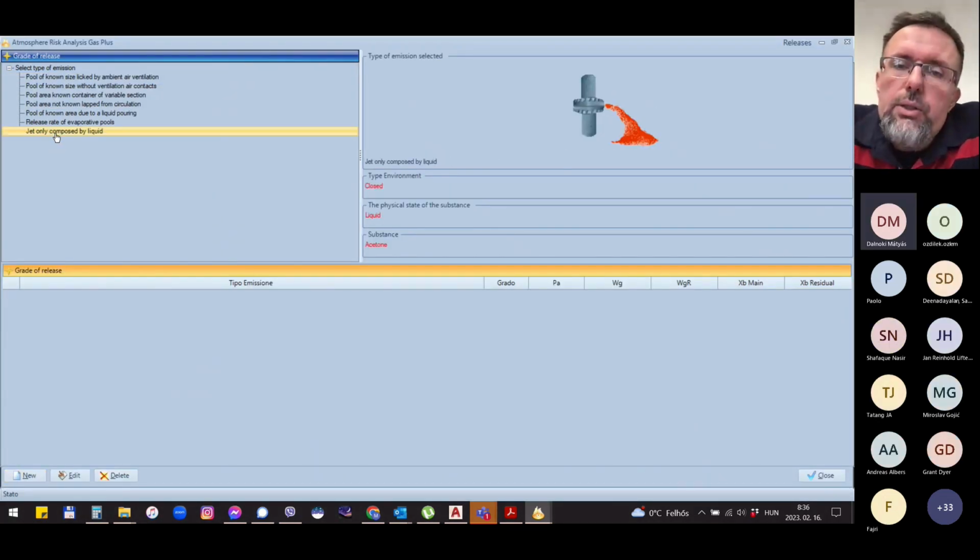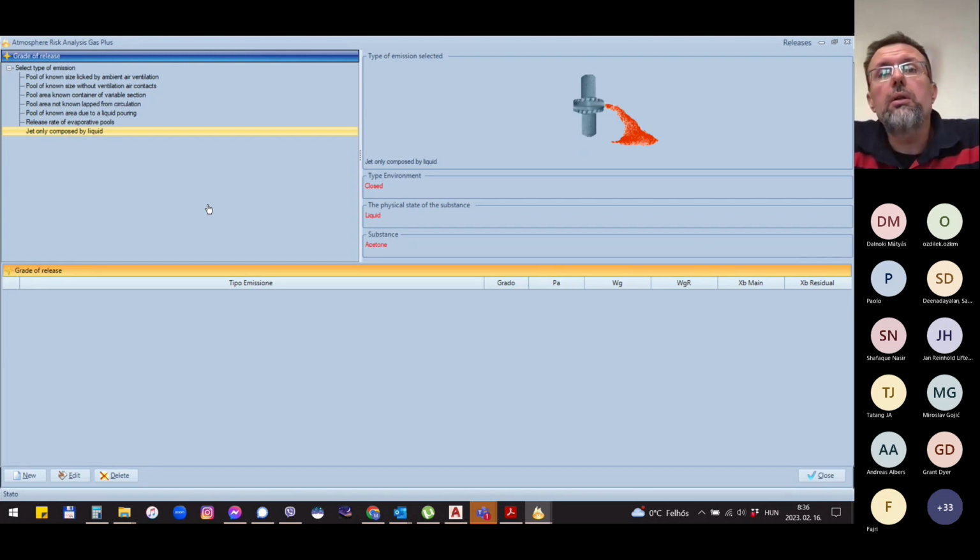So for all releases, you need to do the same procedure, and that's very important. Otherwise, there's another option. You calculate the whole room as one, but in that case, there might be a very expensive solution. So it's always a matter of understanding, a matter of question, which way you go, source of release methodology or the room as one.